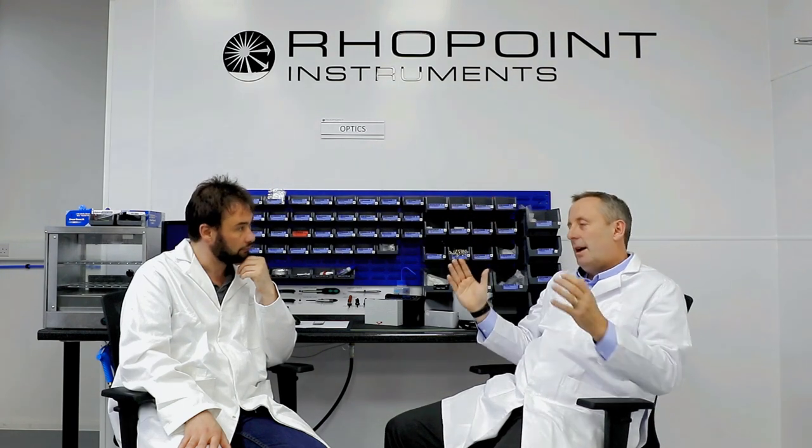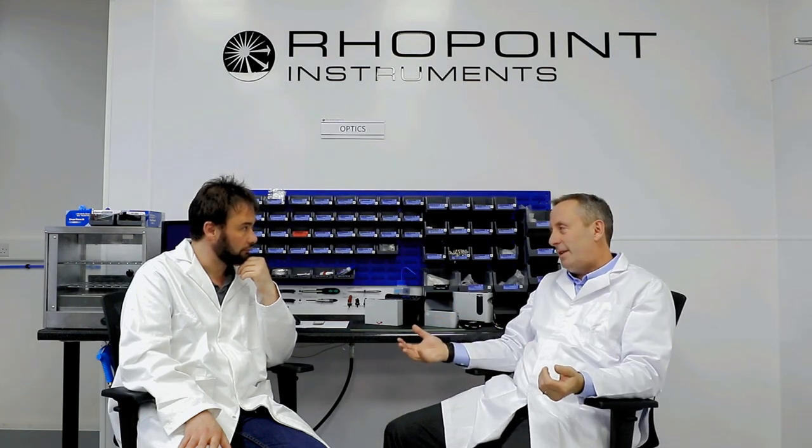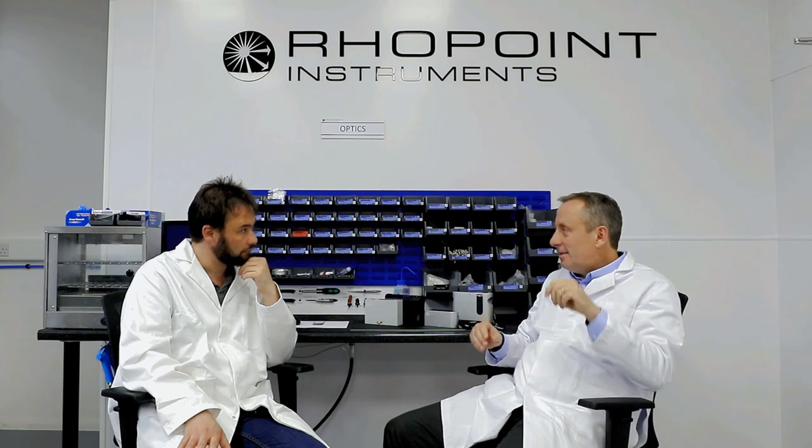And you do that with lenses and focusing, or is it polarized? Exactly. So it's lenses, no polarization, just a collimating lens. It keeps the light straight, it reflects off a surface and it's collected by another lens, and then focused onto a sensor. If it's just a standard gloss unit, it's a diode, which just gives us a number of how much gloss is reflected. And if you're on a more up-to-date kit with the IQ, it's looking at how that light's reflected as well.